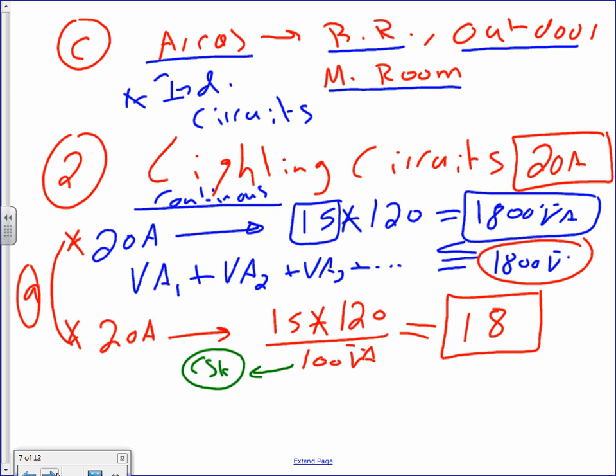Should I allow for future expansion on that one? Some people will say, well, if you need a light, it's easy in the ceiling, guys. If you want to add another couple of lights, it's easy to pull conductors in the ceiling and pick up a couple of lights, another branch circuit basically. So 18 is very conservative. You can even put more on that. So 18 fixtures on one circuit, unless you do the calculation like I did here.